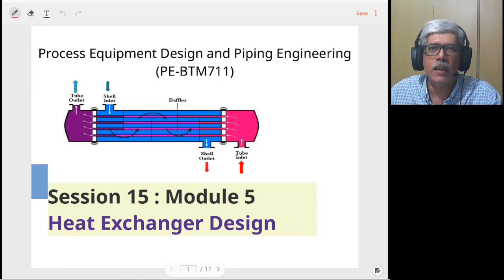So the tube sheet is designed, at a preliminary level, based on the bending load acting on it because of the pressure and shear stress failure of the tube sheet. In both these cases, the tube sheet is considered as a perforated plate because of the presence of the holes. So the ligament efficiency of this perforation is taken into account in these calculations. We have also seen that given the number of tubes, size of tubes and the type of layout, how to estimate the tube bundle diameter, and from that the shell diameter can be estimated.